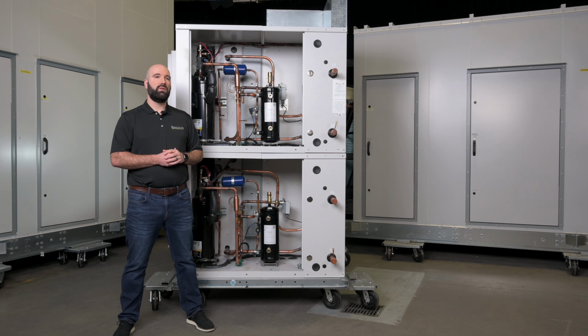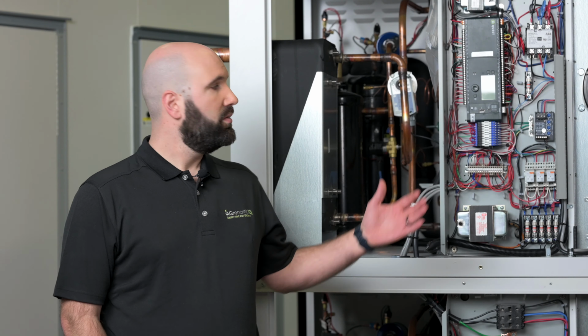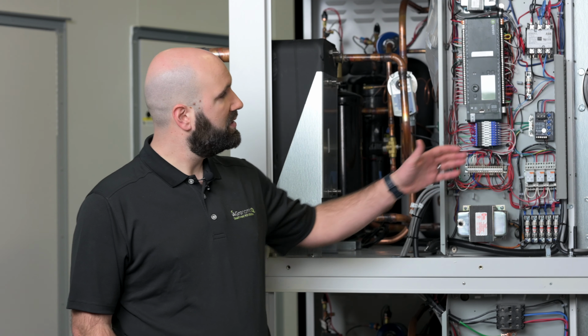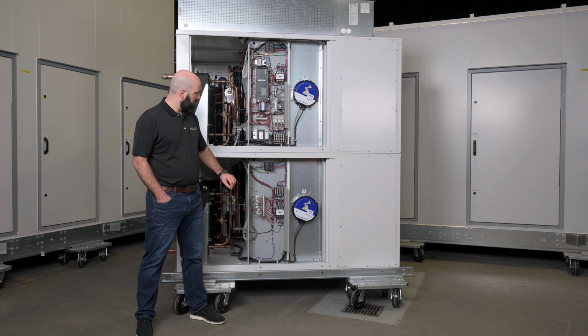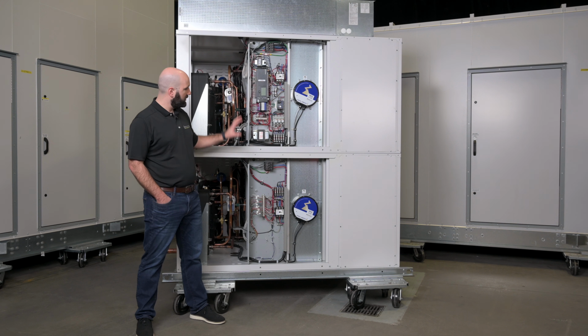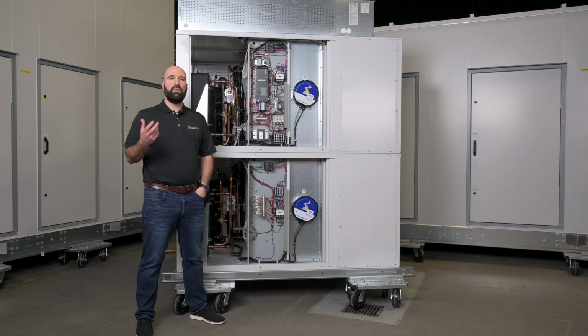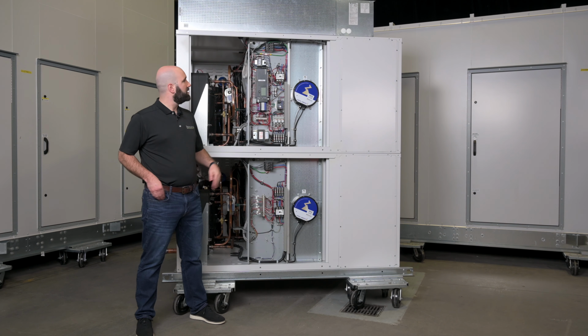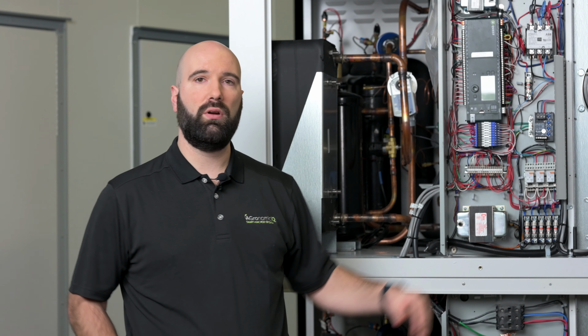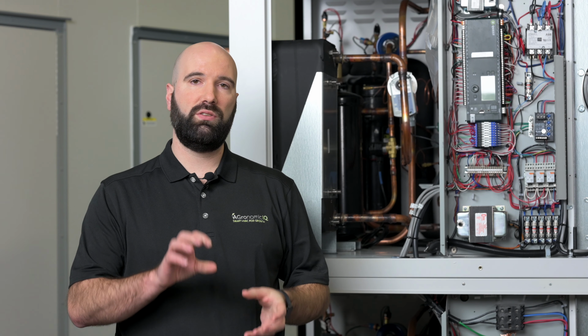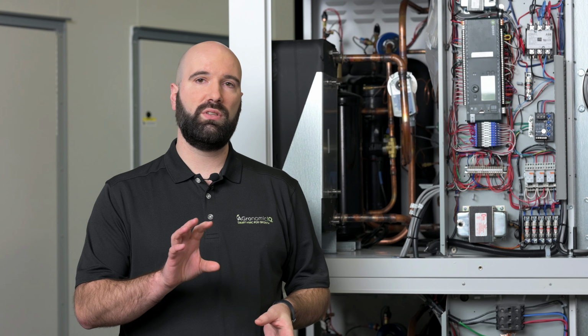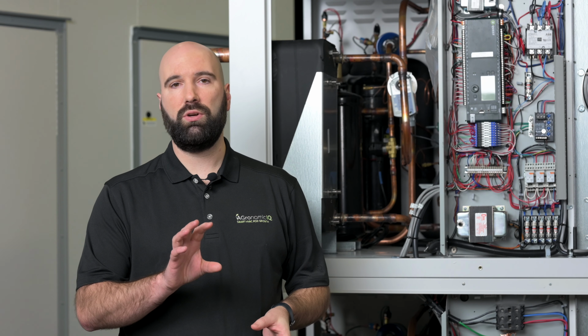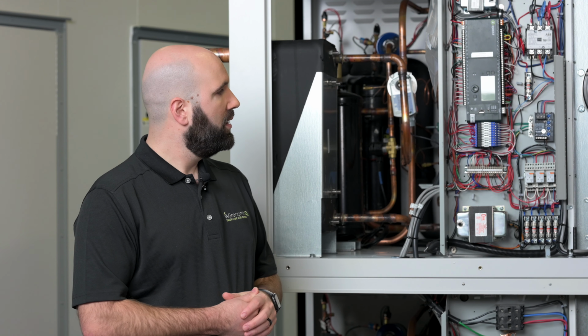We'll take a look at some of the electronics associated. Now that we've spun this unit 90 degrees, you can see the dual blowers, you can see the dual contactors, dual electrical panels. Again, those redundant features amongst those two decks. The only thing shared is the one controller, and that controller allows us to stage those two systems and their overall turn-down capacity together and allow those two decks to work appropriately to service the room.